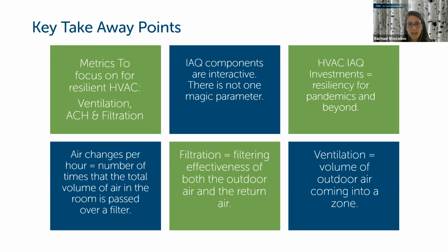In that case, I have seen customers choosing to go to MERV 13 filters, even though they might not need to, since you don't need to filter outdoor air, right? The whole point of filtering the outdoor air with MERV 8 is to keep out the pollens and the particulates and the dust, any contaminants that would just be out in the environment wherever that intake air is. But we certainly don't need to keep viral size particulates out of the outdoor air stream. Customers right now are ordering and replacing that comprehensive filter with a MERV 13 if they can.